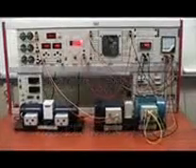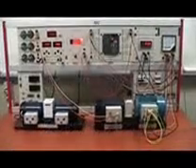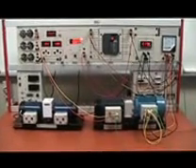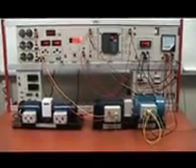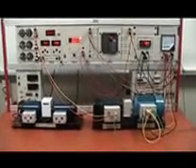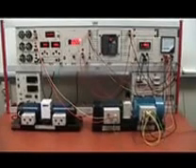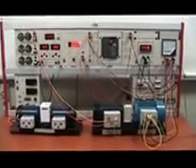For this experiment, we will be finding out the relationship between the input frequency and the output obtained. The initial conditions for a 3-phase motor will be at 0 Hz frequency, 415 volt from the 3-phase power supply, and a load of 200 watts. The motor is in star phase connection, meaning one end of all 3 windings are connected together to form the neutral.